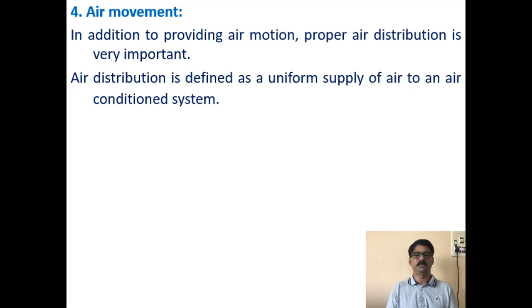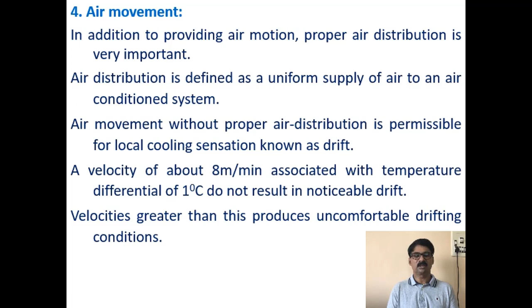Number 4, air movement. In addition to providing air motion, proper air distribution is very important. You see, air motion as well as air distribution. Air distribution is defined as a uniform supply of air to an air conditioned space. Air movement without proper air distribution is responsible for a local cooling sensation known as drift. Suppose there is air movement but without proper air distribution, then it results in a local cooling sensation, and we technically call this drift. A velocity of about 8 meter per minute associated with a temperature differential of 1 degree C does not result in noticeable drift. So 8 meter per minute is the ideal velocity with a differential temperature of 1 degree Celsius, so you cannot observe any drift or local cooling sensation. Velocities greater than this produce uncomfortable drifting conditions.